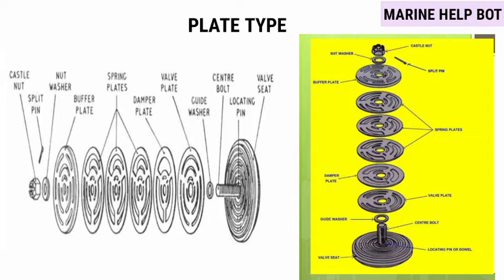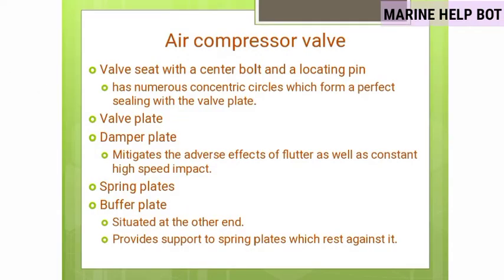The parts of a plate type valve include: buffer plate, spring plates, damper plate, valve plate, and valve seat. The valve seat has a center bolt and locating pin with concentric circles that form a perfect seal with the valve plate. The damper plate mitigates the adverse effect of flutter and constant high-speed impact. The buffer plate is situated at the other end and provides support to the spring plates which rest against it.